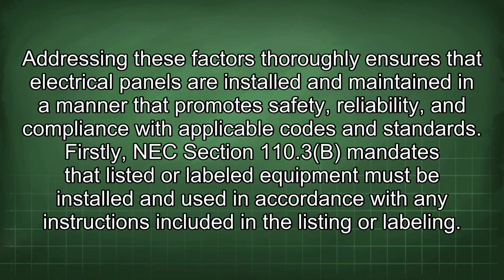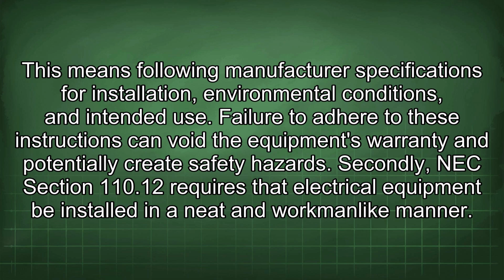Firstly, NEC Section 110.3(B) mandates that listed or labeled equipment must be installed and used in accordance with any instructions included in the listing or labeling. This means following manufacturer specifications for installation, environmental conditions, and intended use. Failure to adhere to these instructions can void the equipment's warranty and potentially create safety hazards.